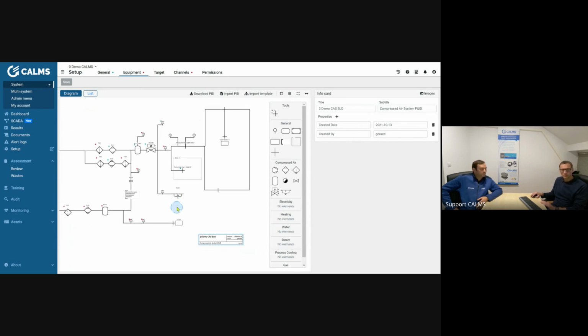I think it might even be switched off. Okay. So then you have here the main ring, yes, we identify, and then you have zone number 1, which is the one with the problems with the pressure drops. That is correct. Okay. And the pipe connecting this from the main header to here, it's a separate one. What is the size? It's 3 inch. Okay. So we now have a basic understanding of the system.